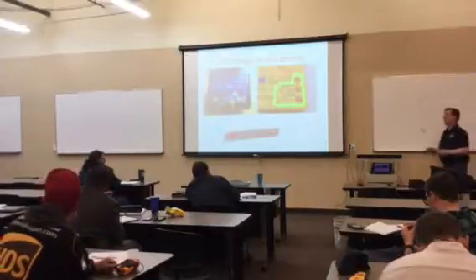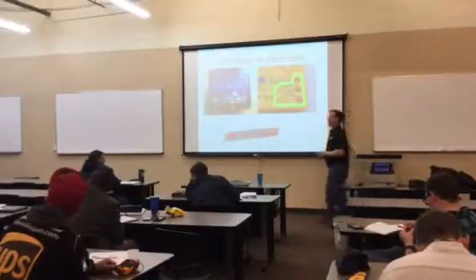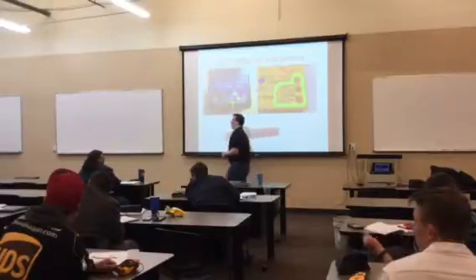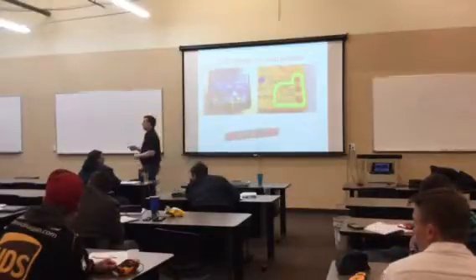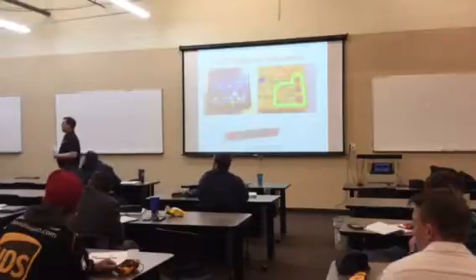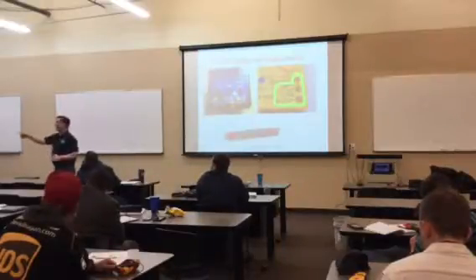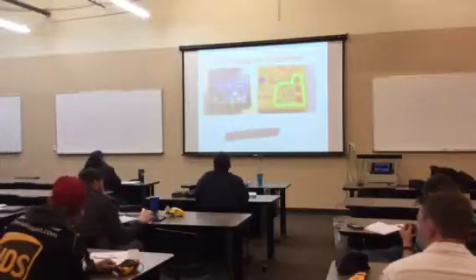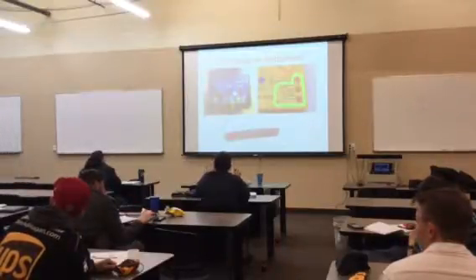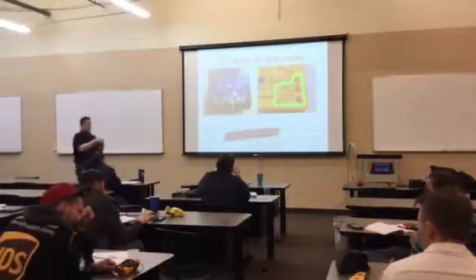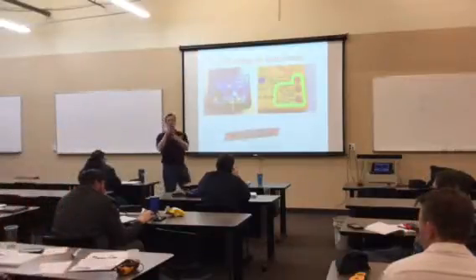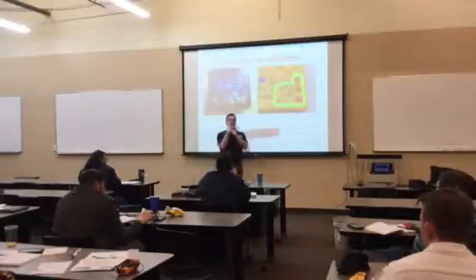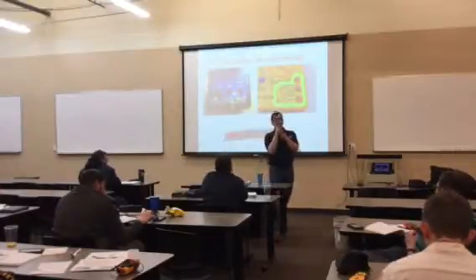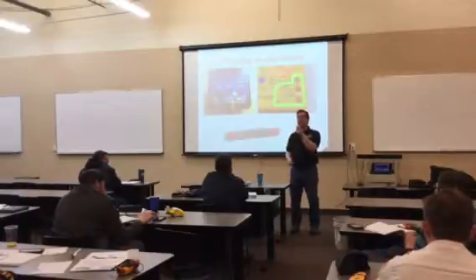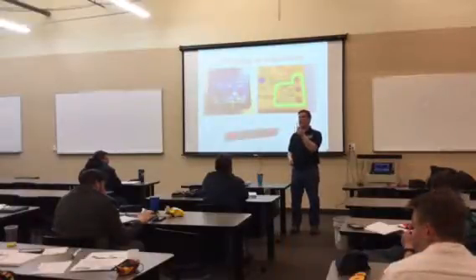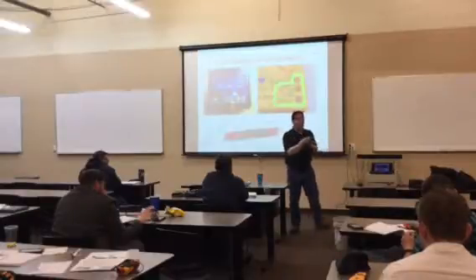Some of my leads here have this piece you can pull off. This set here, which is the Fieldpiece set, says Cat 2 with this off, Cat 3, Cat 4 if that's on. Can I borrow that and pull it up for everyone? These are called tip shrouds. There's only a very small amount, about 3/32 of an inch of bare metal exposed on the end. And this one has a good 1/2 inch, 5/8 of exposed metal on the end. That's the difference of category.